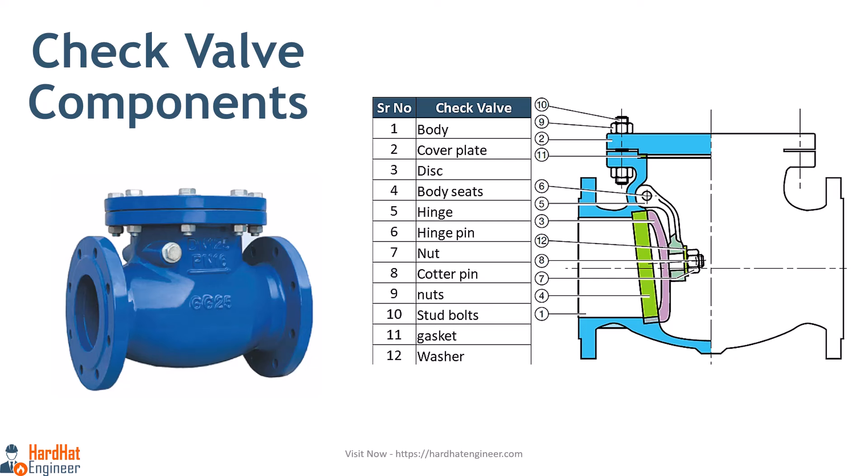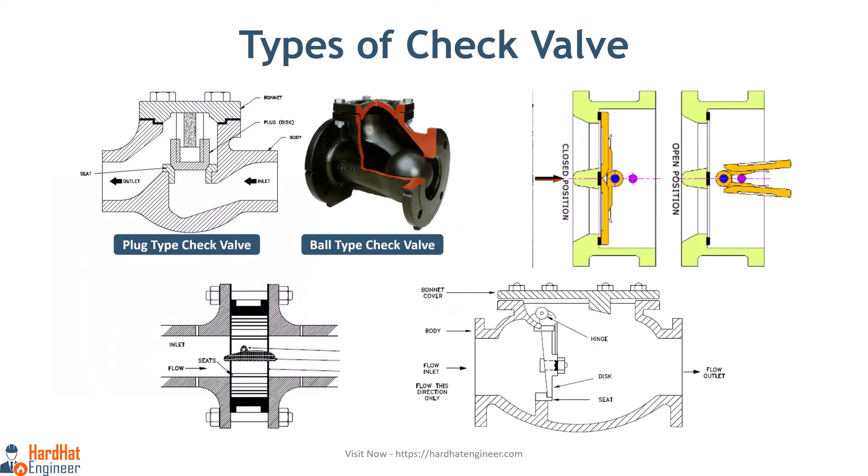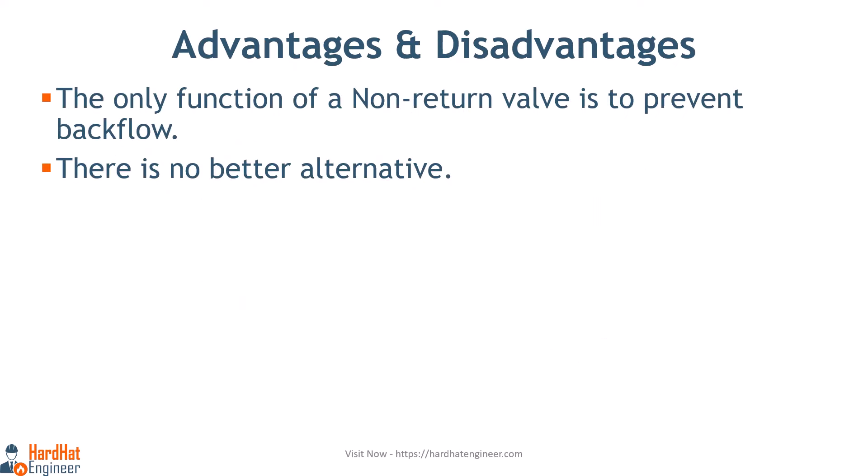Check valves are used in piping systems to prevent backflow. The rotary equipment discharge line, such as from a pump or compressor, is always fitted with a check valve to prevent backflow. The most common types of check valves are swing type, lift type, dual plate type, and stop check valve. The only function of a non-return valve is to prevent backflow — there is no better alternative, though you can choose the best NRV from the various available types.